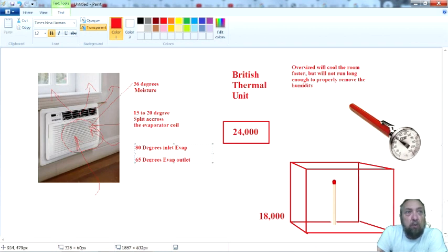So if you went to this unit and the customer is telling you, hey, I just bought this AC and this AC is not cooling, right? So you go to that air conditioner and you say, well, ma'am, before I do anything, I'm going to make these two tests. One, I'm going to check the evaporator to see if the evaporator is filled with Freon. How do I do that, ma'am? I'm going to check all the coils to make sure that they're cold to the touch, not room temperature, and they should start collecting humidity. And the whole evaporator, if you put your hand on it, is going to get wet as it draws the moisture out of the air.